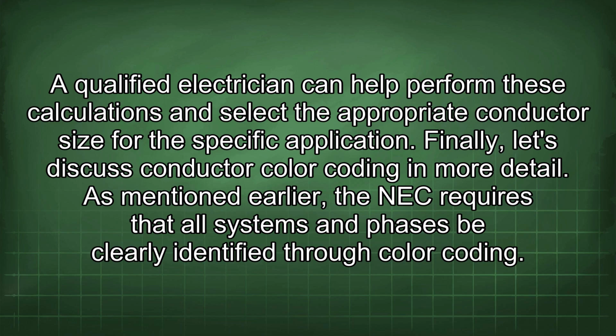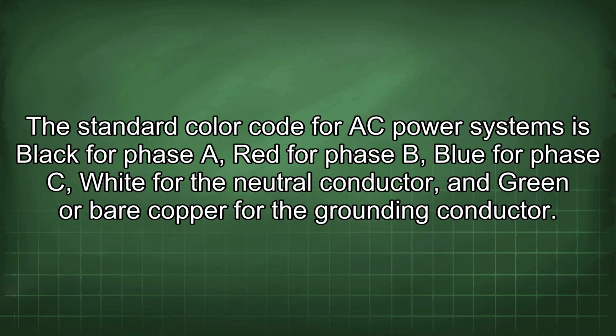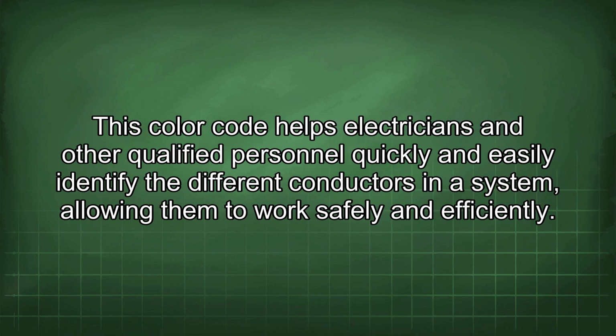Finally, let's discuss conductor color coding in more detail. As mentioned earlier, the NEC requires that all systems and phases be clearly identified through color coding. The standard color code for AC power systems is black for phase A, red for phase B, blue for phase C, white for the neutral conductor, and green or bare copper for the grounding conductor. This color code helps electricians and other qualified personnel quickly and easily identify the different conductors in a system, allowing them to work safely and efficiently.